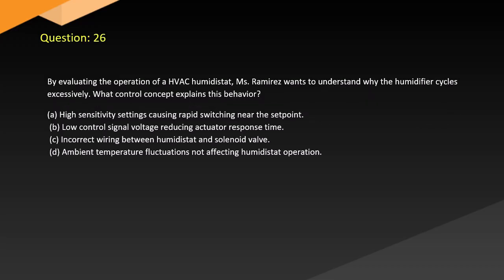Question 26. By evaluating the operation of a humidistat, Ramirez wants to understand why the humidifier cycles excessively. What control concept explains this behavior? A. High sensitivity settings causing rapid switching near the set point. B. Low control signal voltage reducing actuator response time. C. Incorrect wiring between humidistat and solenoid valve. D. Ambient temperature fluctuations not affecting humidistat operation.